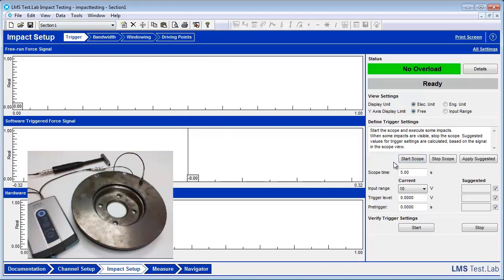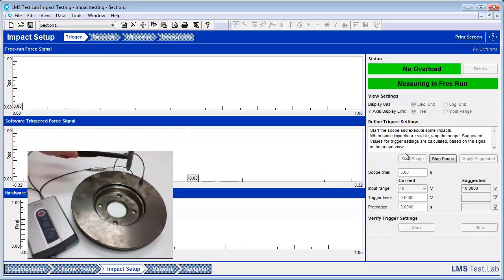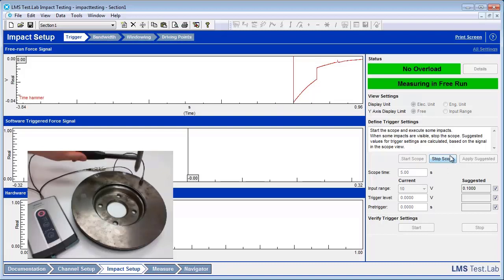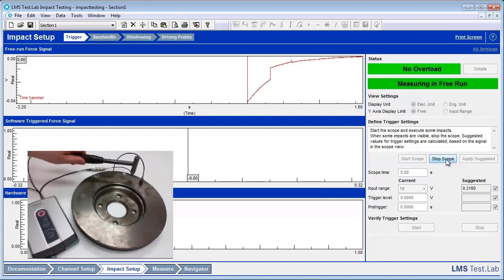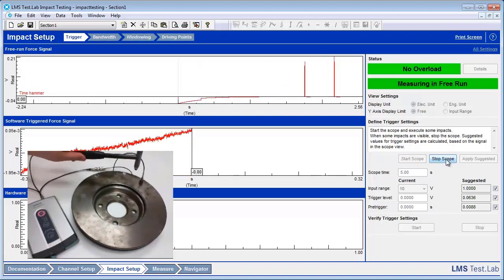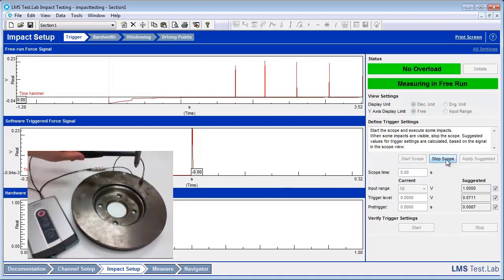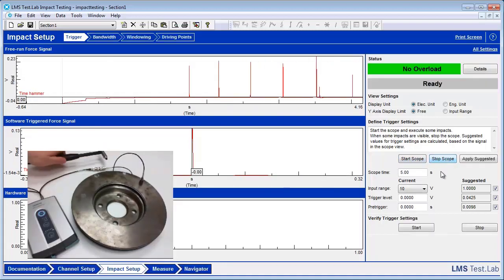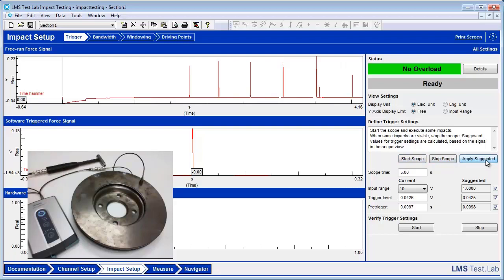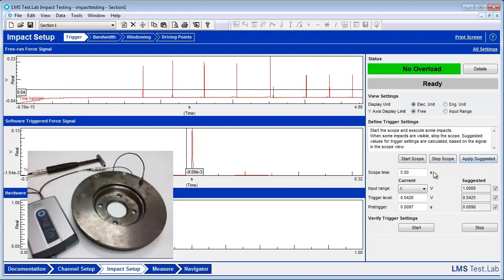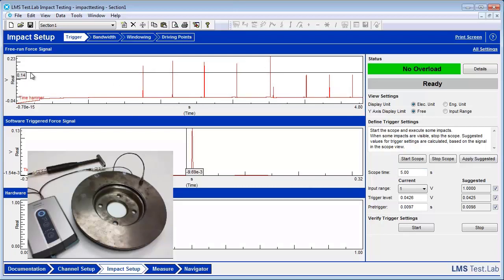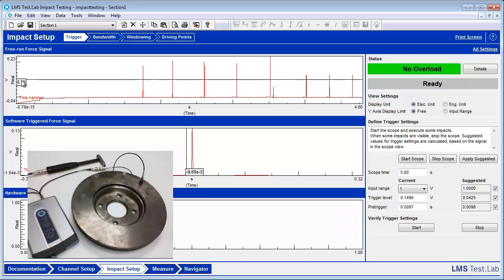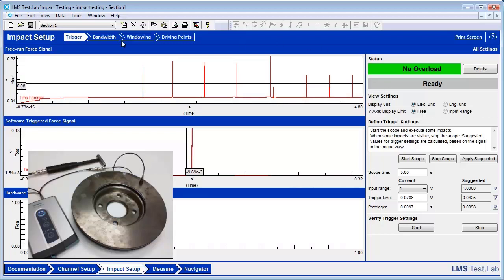First one is going to be Trigger. This is where Test Lab is going to try to figure out a good trigger level for our measurement. We can do this by Start Scope, hitting the object multiple times, pressing Stop Scope, and doing Apply Suggested. As we can see, Test Lab adds this little black line here, which is their recommended trigger level. If need be, we can come in here and manually change this.